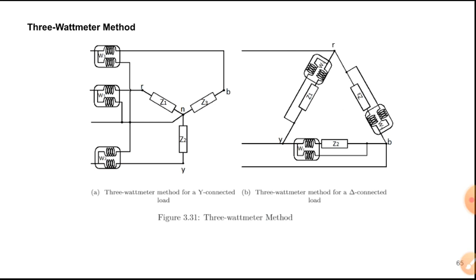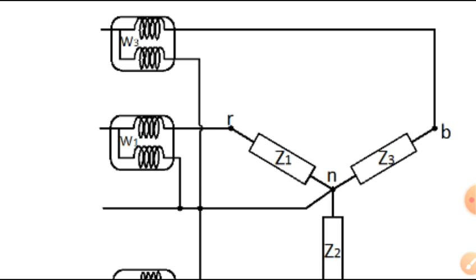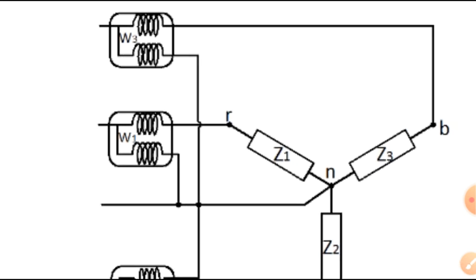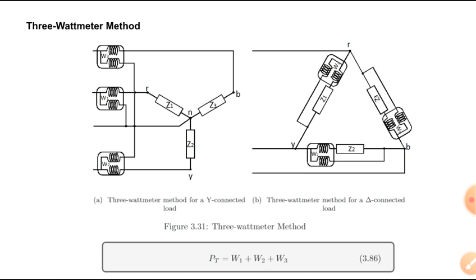For the 3-wattmeter method, we use 3 wattmeters — one at each phase of the three-phase system. In Y connection (letter A) and delta connection (letter B), we have W1, W2, and W3 connected at each phase. Observe the connection: the current coil is always in series with the path of the current, while the voltage coil is in parallel with the phase voltage of the load. The total power is W1 + W2 + W3.